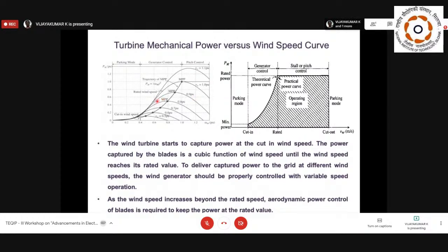My wind velocity is the same, but if I'm operating my machine at 0.6 per unit, my output power is also 0.5 per unit. So you can operate your turbine at any speed; your turbine speed may locate here, here, or here. At that time, my turbine output power is less as compared to this point. If I'm operating my turbine at 0.9 per unit, my output power will be 0.75 per unit. At this particular point, my power output from the turbine is maximum.